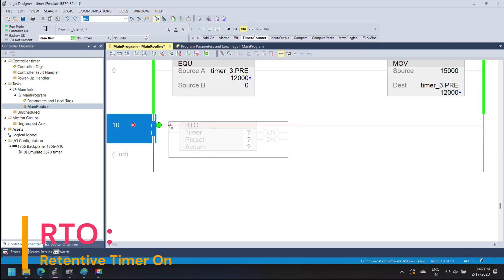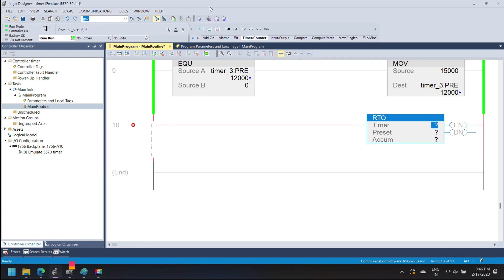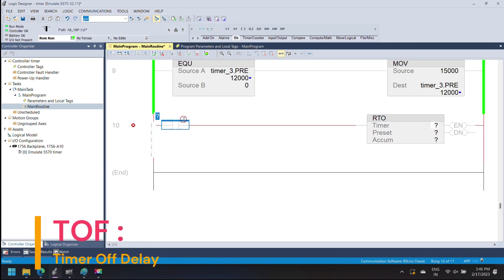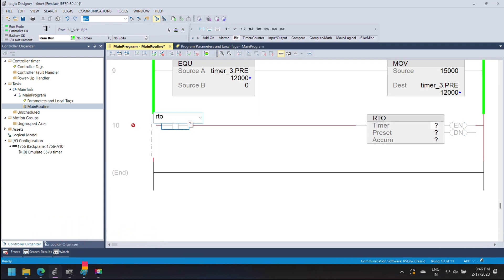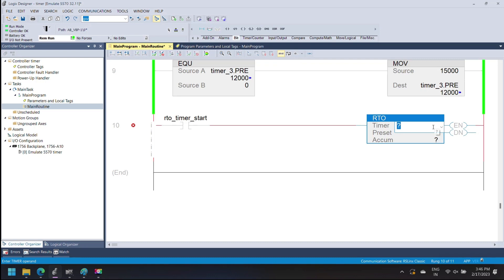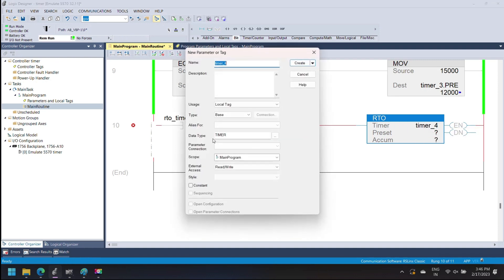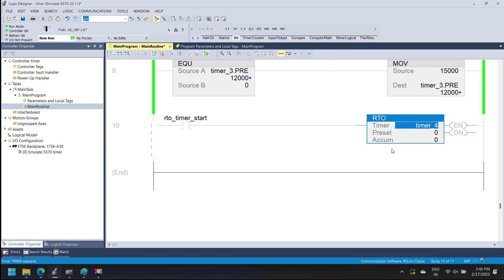Timer On Delay and Timer Off Delay are non-retentive timers. In a retentive timer, the accumulator value is stored while the input condition changes from true to false. If the input condition changes from false to true again, the timer starts from the stored accumulator value until the preset value equals the accumulator value and the timer done bit is set to true. If the timer done bit is set in a retentive timer and the input condition changes, the accumulator value is not increased until you reset the timer using the reset instruction.